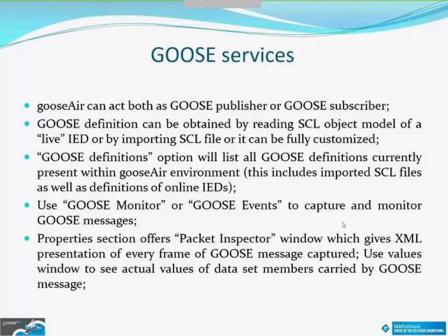The GOOSE monitor is also linked with the gooseAir property section, which in this case gives an XML presentation of every frame of GOOSE message captured. Something similar to what Wireshark is doing, it presents them in the exact order in which frames are sent by the server, which I think is very useful, especially for troubleshooting purposes, and also for 61850 beginners to see the exact structure and content of a GOOSE message.